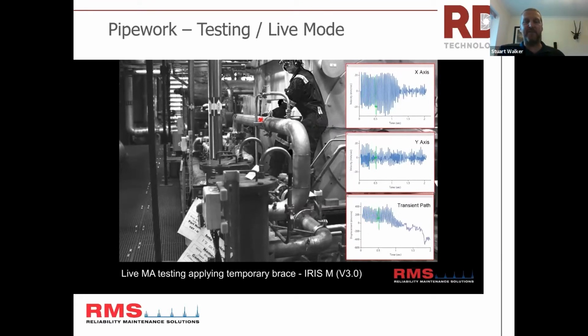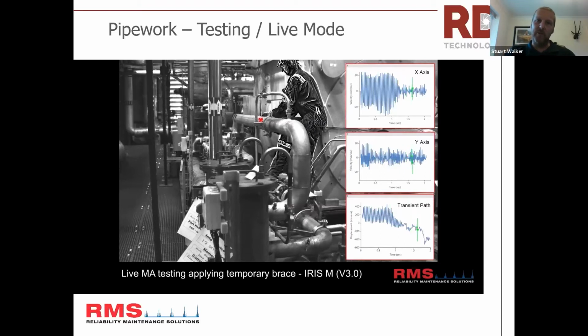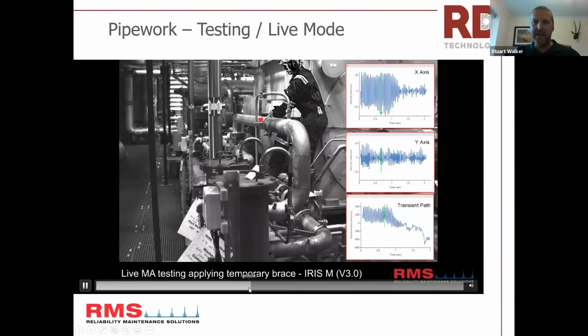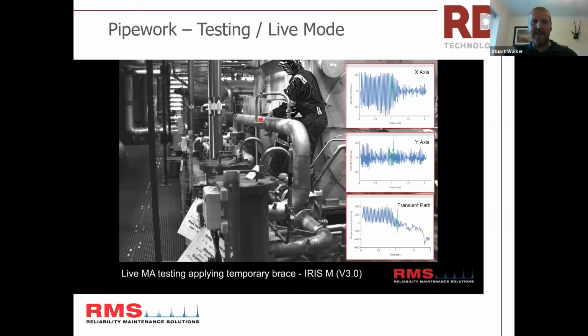Now this, Jeff, was absolutely key on this job. This is adding some bracing later on. This is in live mode. Keith there has a temporary brace, and he's tightening it up. If we play that one back, Jeff, you'll see the vibration just die. So imagine I'm on this job and I'm saying, Keith, tighten it up, and he does that, and then boom, we've killed it. We've changed the natural frequency.